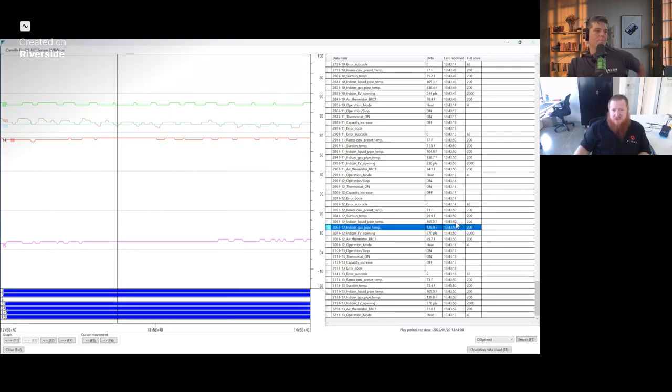which it seems really hot, but one of the things that often is forgotten about is heat radiation, right? So that pipe at the compressor is saying it's 200 degrees, all of that stuff's connected. So the amount of refrigerant that's flowing through that discharge line into the indoor, into the branch selector at this point, because this is heat recovery, I'm sure it's hot up into the branch selector, and then we're just slowly losing our heat as we get to the indoor units.